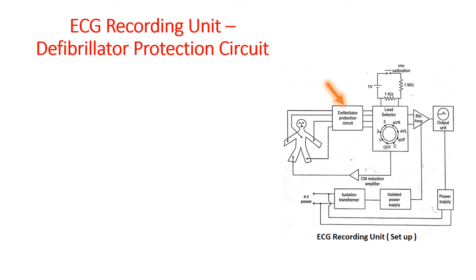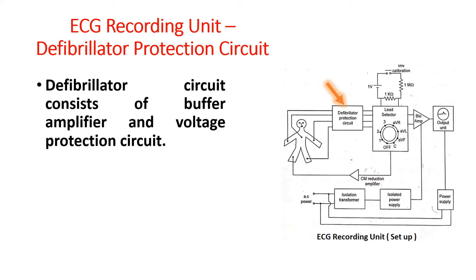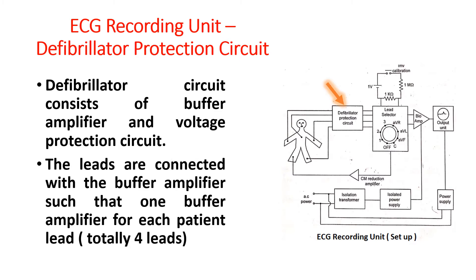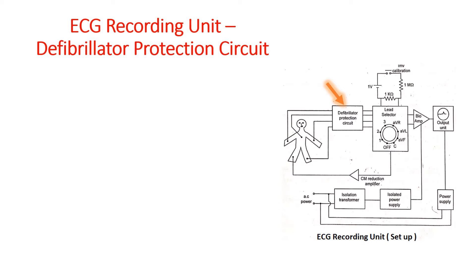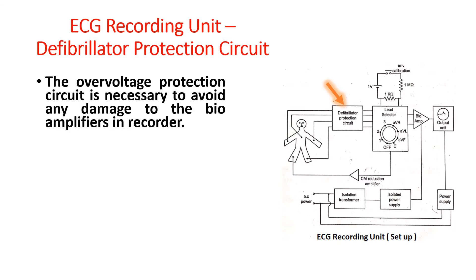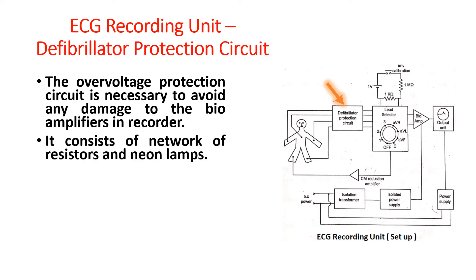Defibrillator protection circuit. It consists of a buffer amplifier and overvoltage protection circuit. The leads are connected with the buffer amplifier such that one buffer amplifier is used for each patient lead, totaling four leads. The overvoltage protection circuit is necessary to avoid any damage to the bioamplifiers in a recorder. It consists of a network of resistors and neon lamps. The lamp fires when a pulse from a defibrillator is present; during firing of the neon lamp, there is no output to the preamplifiers of the recorder.